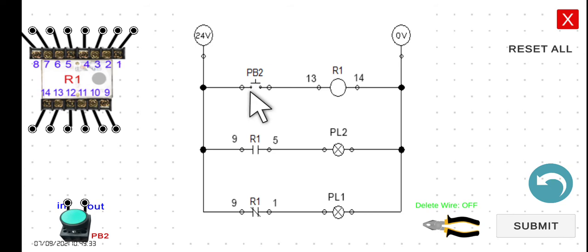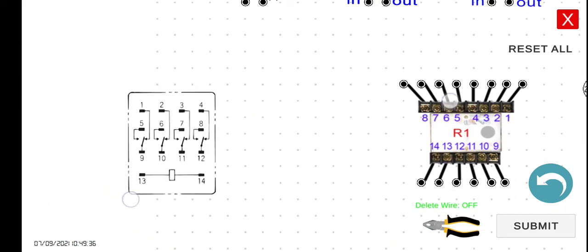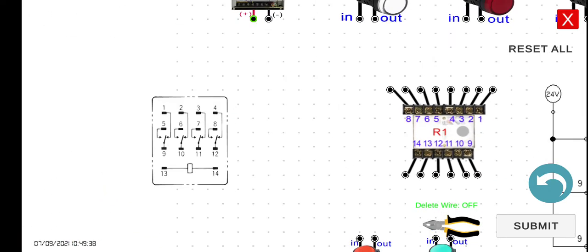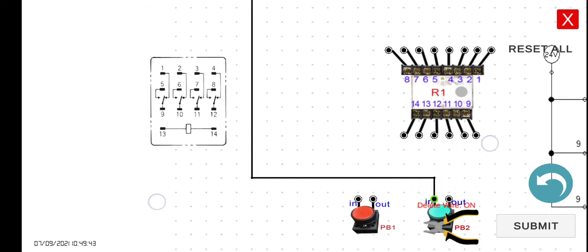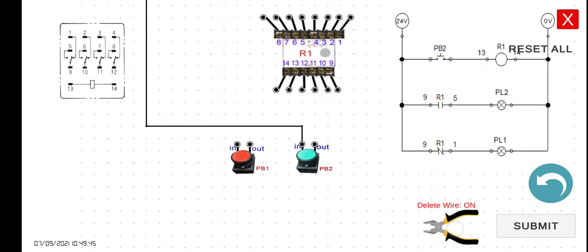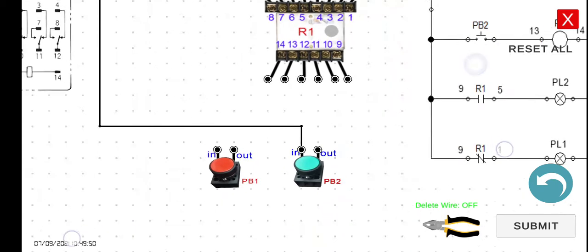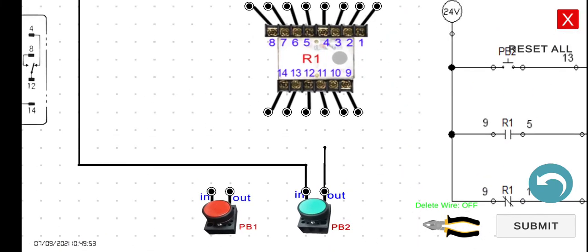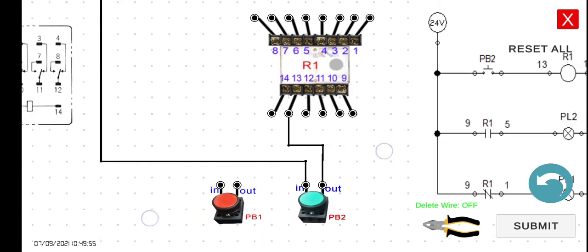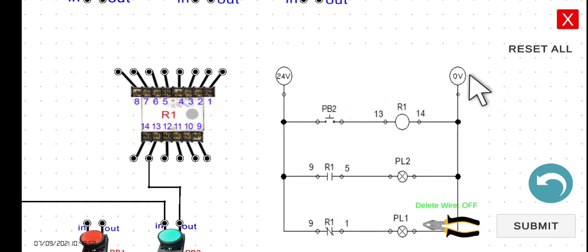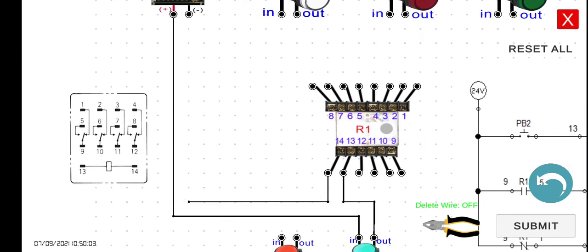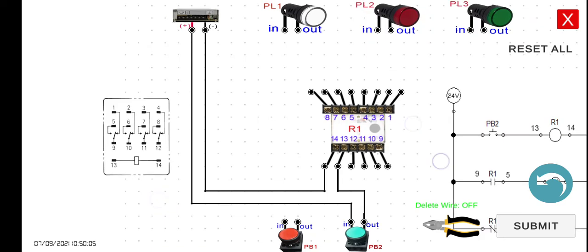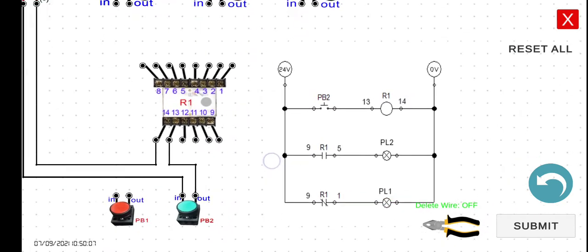Now let's connect the wires. Connect 24 volts to the input of PB2, then connect the output of PB2 to terminal 13. This is very similar to what we did in the previous activities. Then connect terminal 14 back to the zero-volt (negative) terminal of the power supply. That completes the first rung.